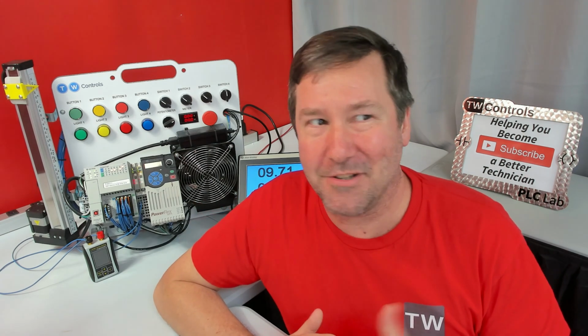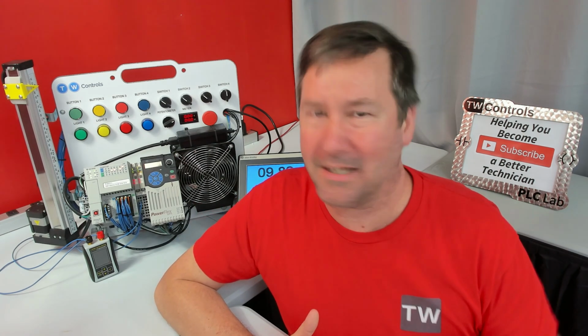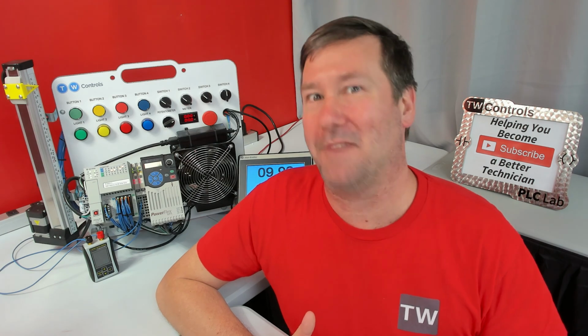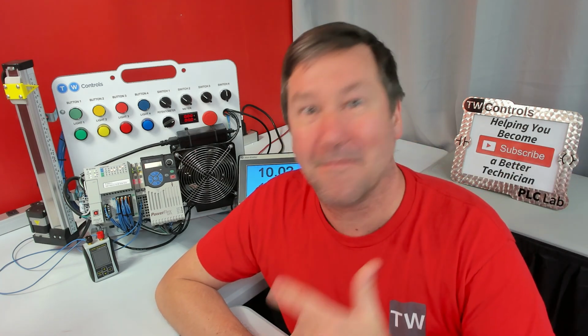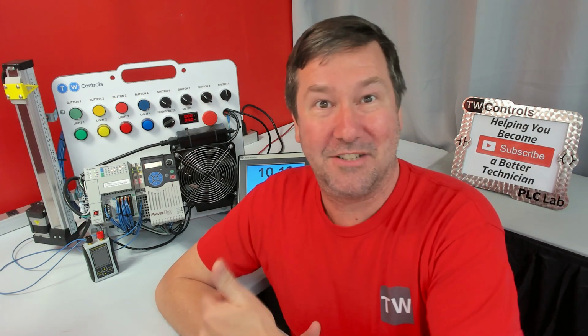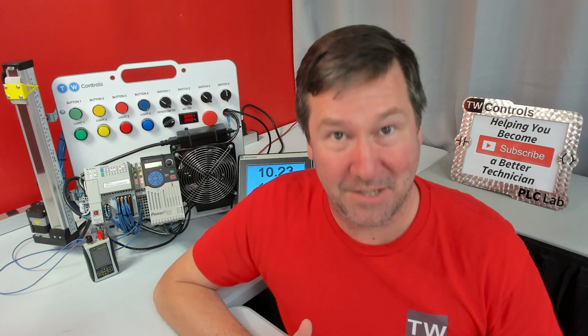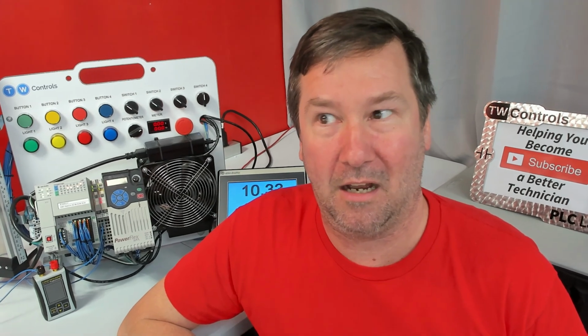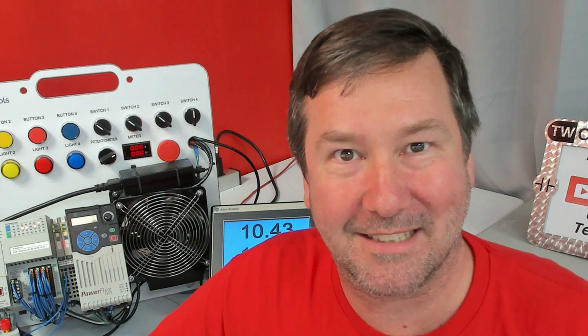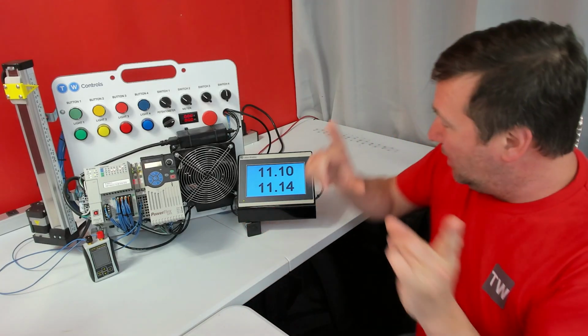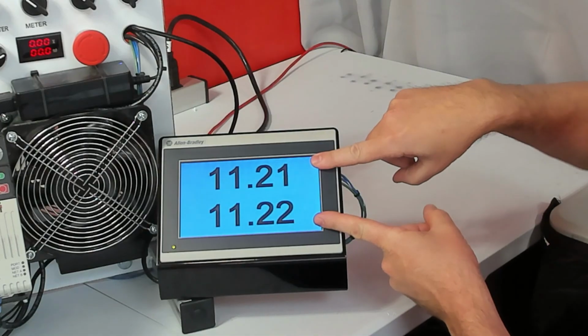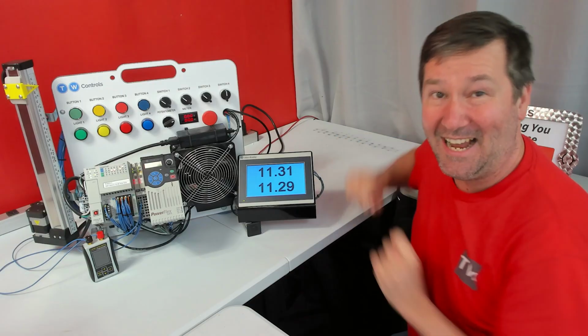He said, it's our pump pressure. Okay, how is your pump pressure controlled? And he's like, well, a PID. I'm like, all right, what is it reading for its process variable to get you that pump pressure adjustment? And all of a sudden he's like, that same analog signal. So my goal for this video is to explain to you why these two values don't match and how they can be affecting your process.